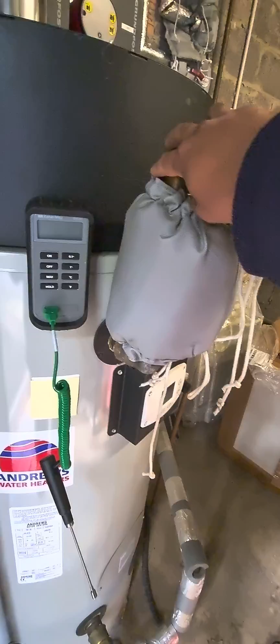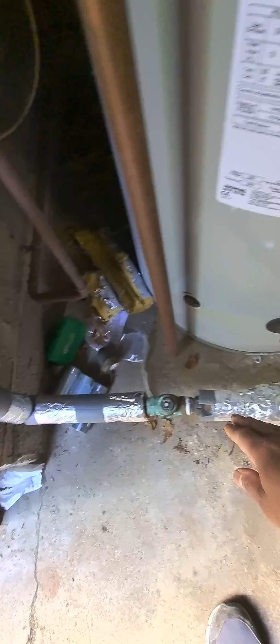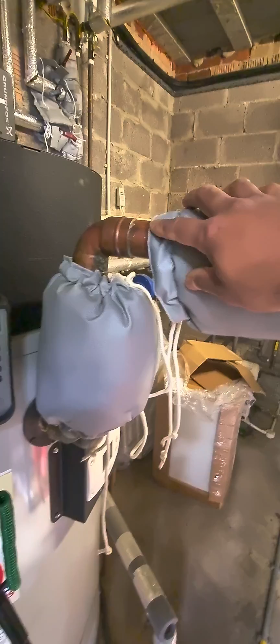heater. So you can see, this is the flow pipe. This is the flow and this is the hot water return. The hot water return goes up to here, and then it goes inside the water heater. But from this part, this is the cold water inlet, which meets here at the T. So if you have a situation like this, then you can take the temperature here for the return and here for the flow.